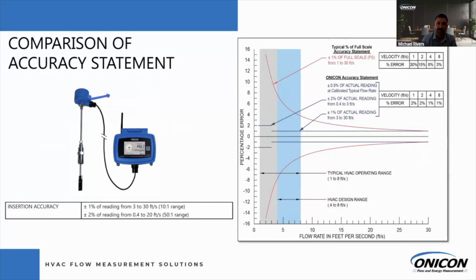So as you can see, at 4 feet per second, that 1% of full scale device is plus or minus 8%. And then when you talk about domestic water or makeup water applications, now you're dealing with velocities down to like 1 foot per second. Well, that 1% of full scale device is plus or minus 30%, while we're maintaining 1% over that very wide range and then 2% at the low end.